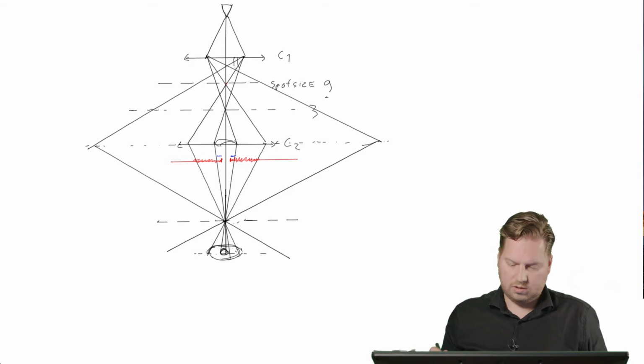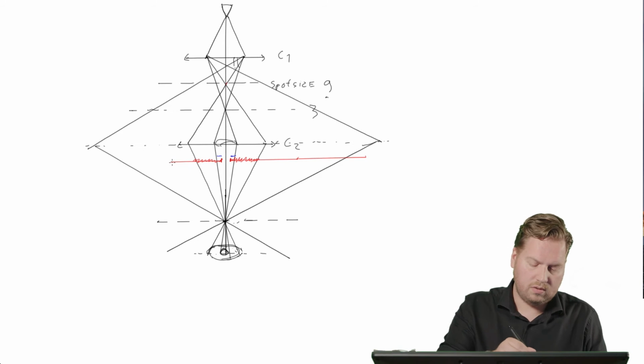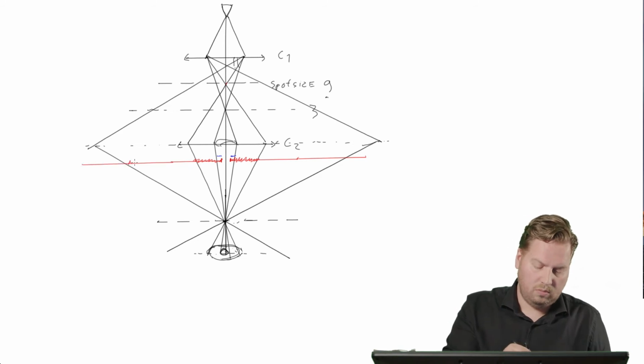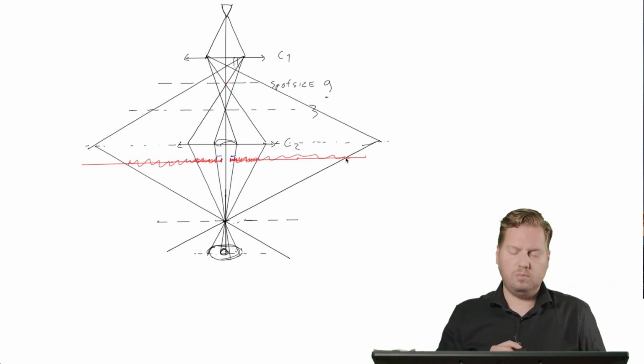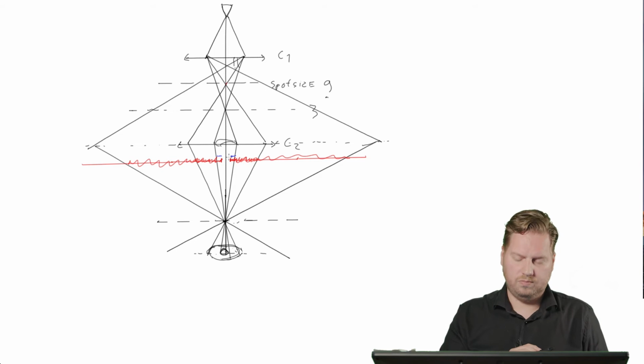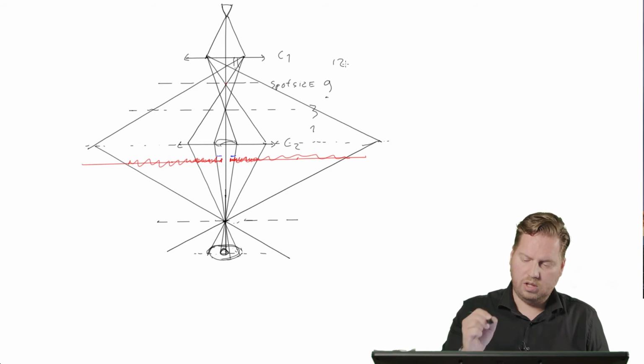You can easily understand that now, oh, this is my aperture. Almost all of the light here, almost all of it, is being blocked by this aperture. So if you increase spot size, the spot size goes up from spot size 1 to spot size 12. You will see that this crossover moves up.